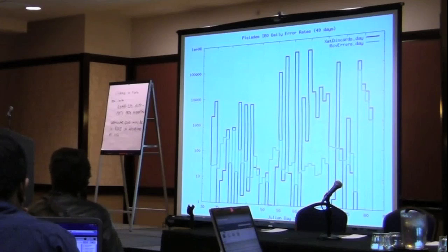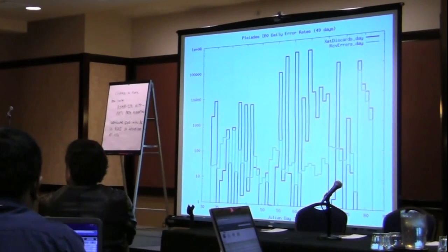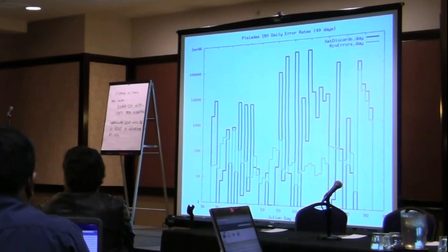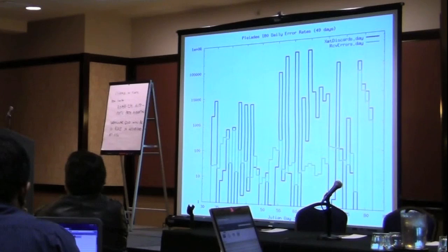One issue that we've seen is you'll get a batch of 1,000 cables, and 500 of them will be below margin, and they'll show error rates higher than the rest of the batch. So you weed those down, and you might replace 200 that have the worst problems, but you still have 200 in there that are flaky occasionally. It's pretty disruptive and time consuming to replace 200 cables. Over time we get new batches of cables and try to weed them out, and there may be temperature variations.